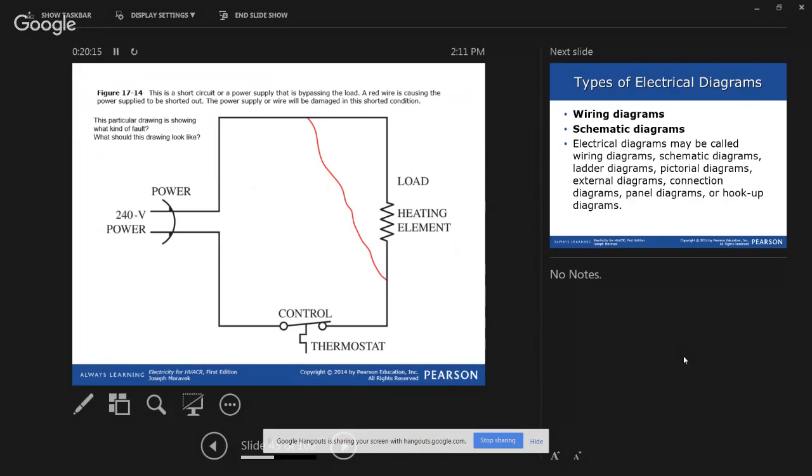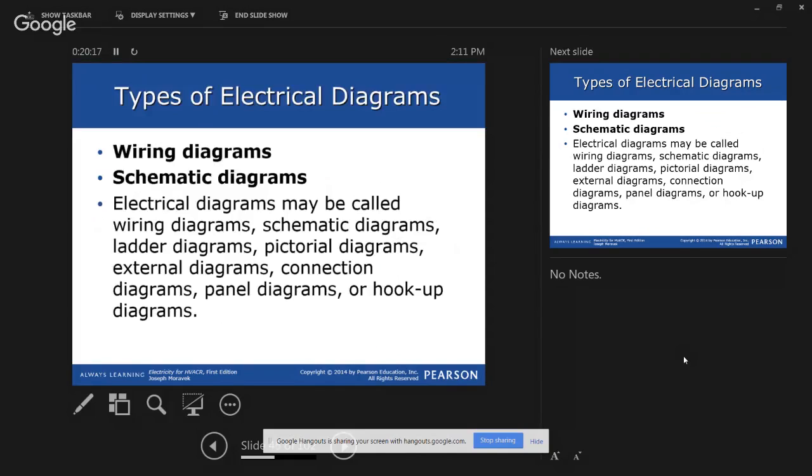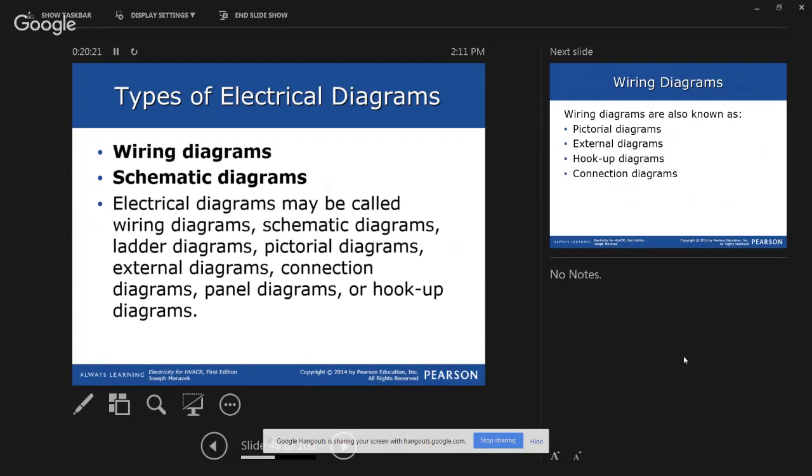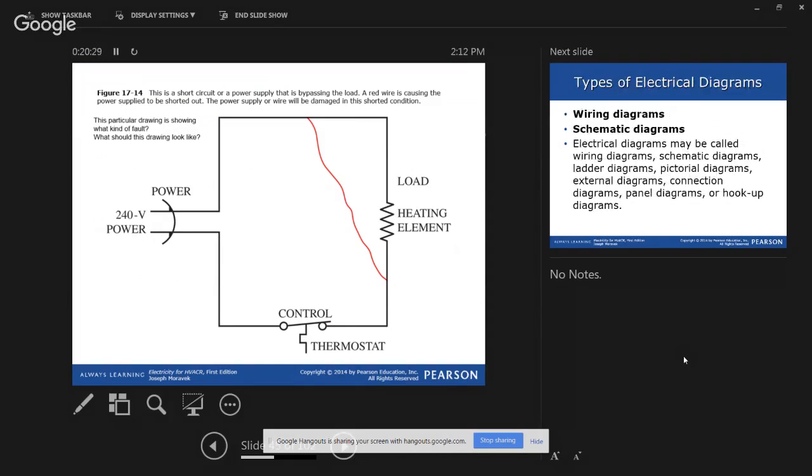All right, moving forward. Yeah, it's at 17-1. It's supposed to be figure 17-1750. It's at 1714. Yep. It's looking around, like in the book, it has both. Okay. All right. Well, way to go for having the book, my friend. So good on you. But no, this is when I was prepping for this. I noticed this. I'm like, oh, whoa! I need to make sure that my guys realize that this is definitely not a ground fault case. This is a short. And what should a ground fault look like? So that's why we went over here for this.